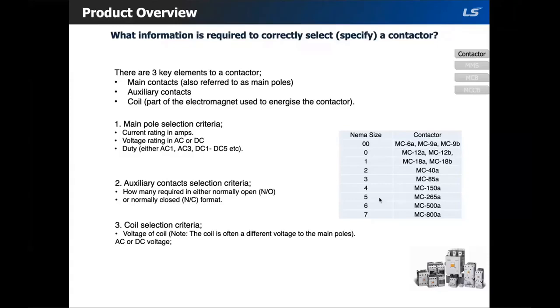So, in order to select the correct contactor, you will need to know the main pole. So you will need to know the current rating, and then the voltage rating in AC or DC, and finally the duty either in AC1 or AC3 or DC1 through DC5. So AC1 would be your low inductive load, AC3 would be your higher inductive load. So in absence of a specific duty, a full description of the nature of the electrical load would be required.